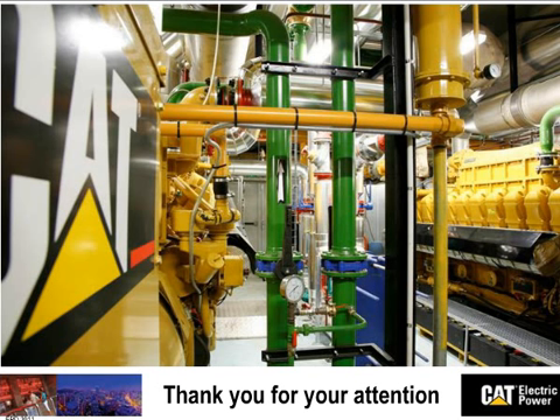Okay. So in more details, the high heat value contains the water that is embedded in the methane, and the low heat value doesn't have that. It's about 10% difference of heat, the latent heat of water between LHV and HHV, and that's why we have this 108, because we can recover with the heat pump and the condensation. We can recover this latent heat. I don't want to be too complex on the thermodynamics here, but it's 108% on LHV. That's correct number. It's good, no?